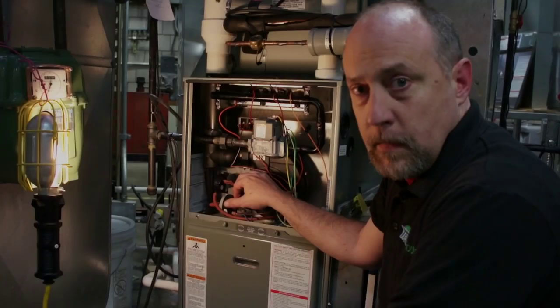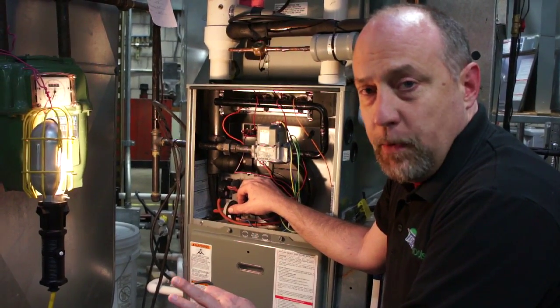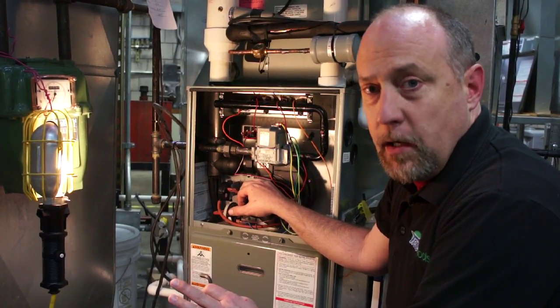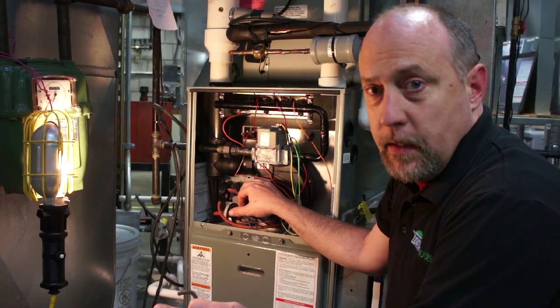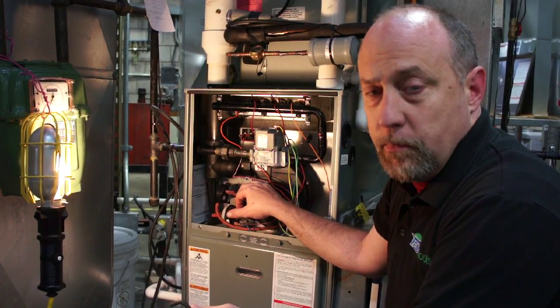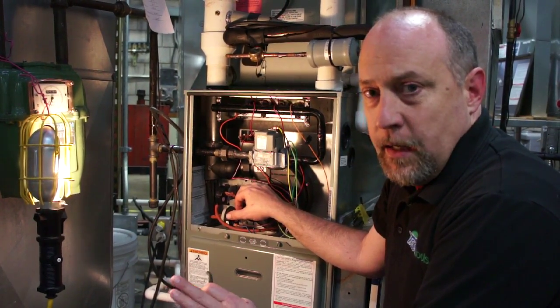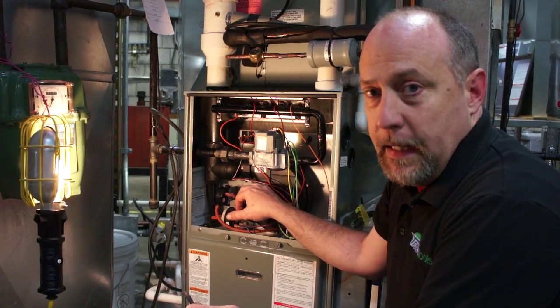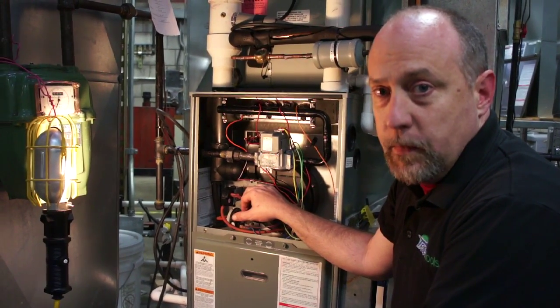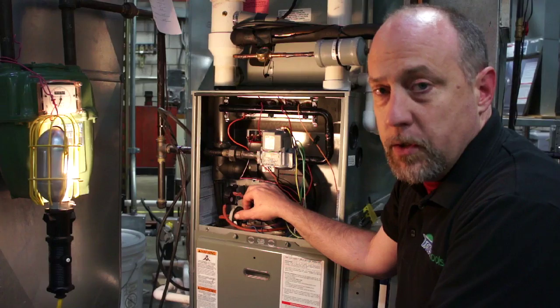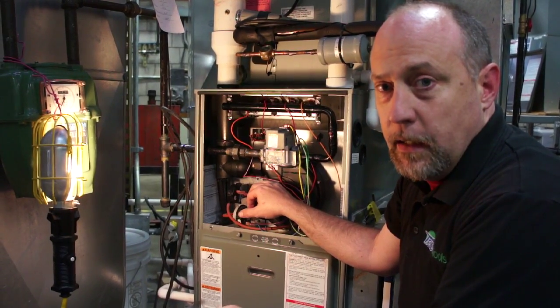All right. On furnaces like this 90 plus, ideally we would be making our combustion test outdoors at ground level if it exited the home through a side penetration. A lot of times though that's not possible, and it terminates to the roof, and we have to drill a hole in the flue pipe in order to do a combustion test, and that's the case of this 90 plus right here.